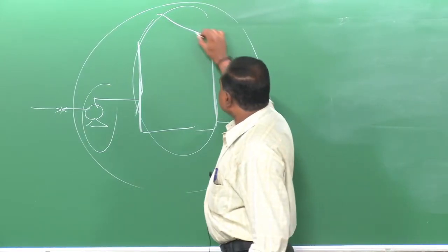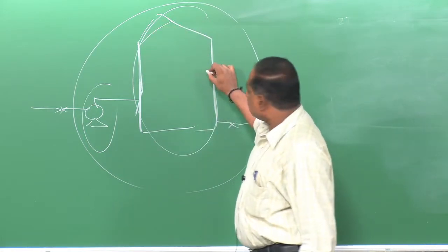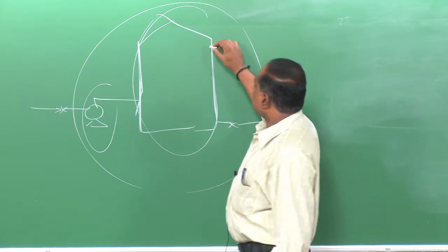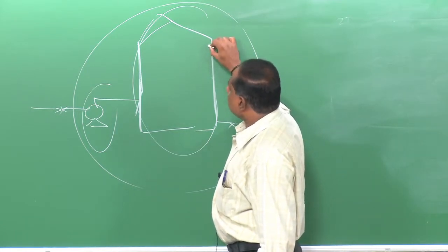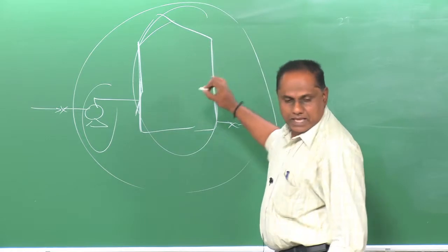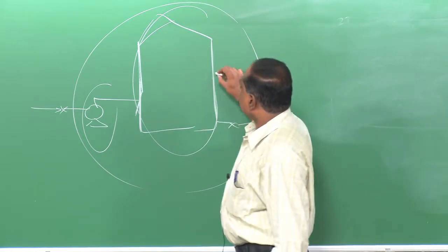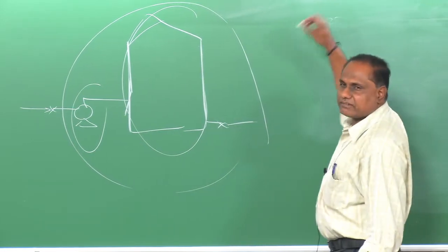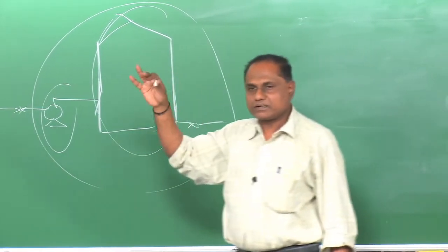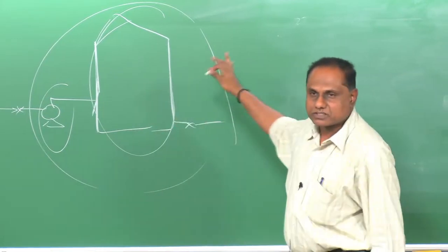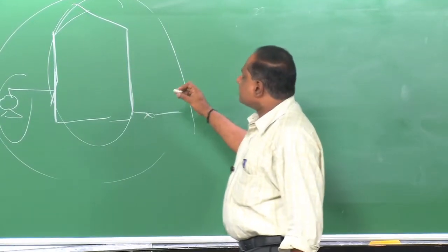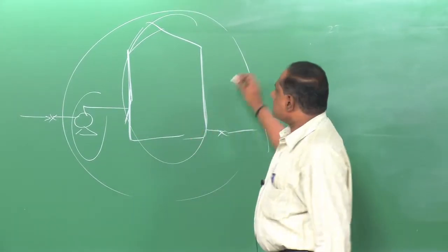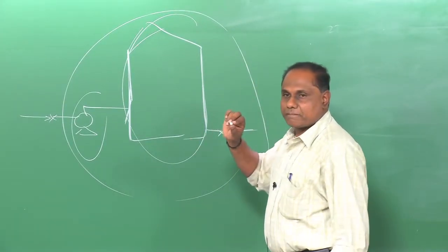define the design intent of it. Say if you are taking this tank, define the design intent of this tank, maybe in terms of process parameters, level, temperature, pressure, whatever the design intent of it is, and select the parameters, chemical parameters, what I had told earlier: temperature, pressure, level, flow, composition, different parameters that can occur in this process area. So we have to find a deviation from the design intent. We do this by using guide words. There are 7 basic guide words.